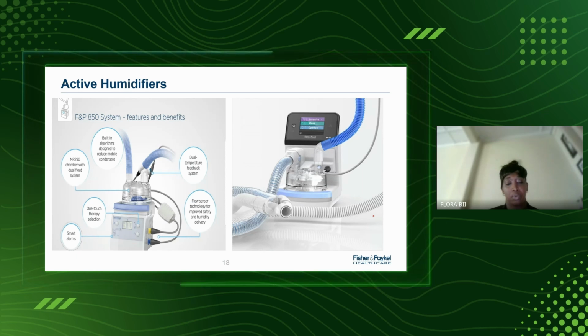Now the temperature and flow probe, which is blue in color, is majorly for doing two roles, and that's why we've indicated here that it has a dual temperature feedback system. The temperature and flow probe is responsible, one, for checking the temperature of the gas leaving the humidification chamber. But it also has another patient end, at the end of the circuit, and that one checks the temperature being delivered to the patient. By having a dual temperature feedback system, it ensures that the gas delivered to the patient is optimal: 37 degrees centigrade and 44 milligrams per liter of humidity.